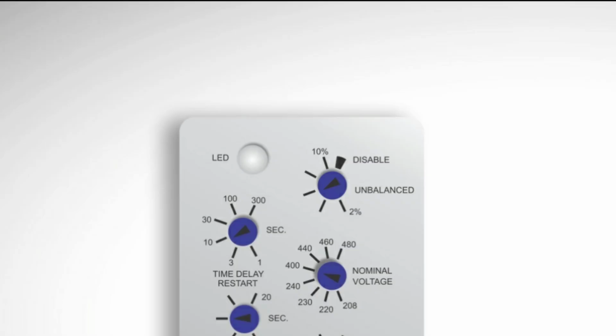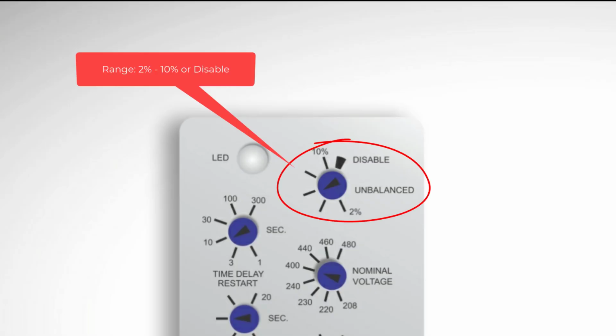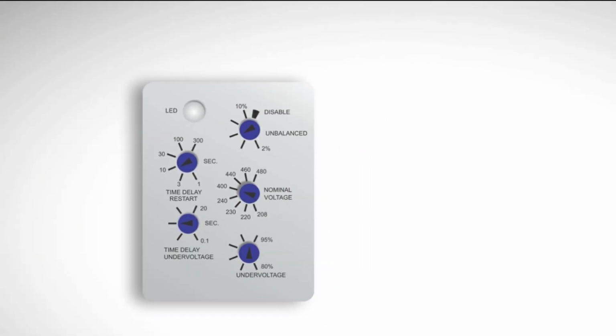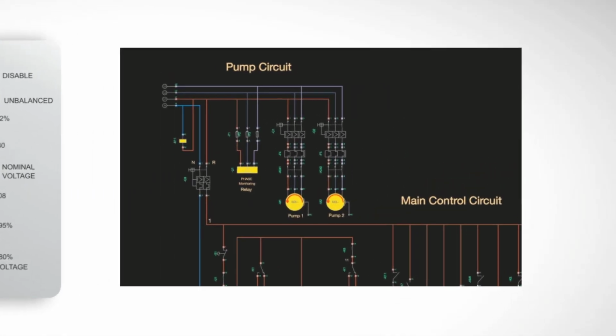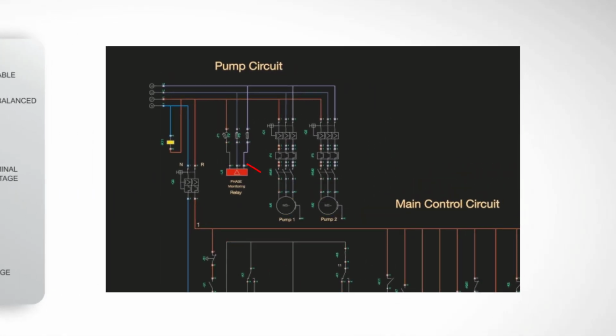This knob controls the unbalance percentage, range 2% to 10% or disable. It detects voltage differences between phases. Example, if one phase drops too much compared to others, the relay trips. Lower percent equals more sensitive and higher percent equals less sensitive. Important for protecting motors from overheating.